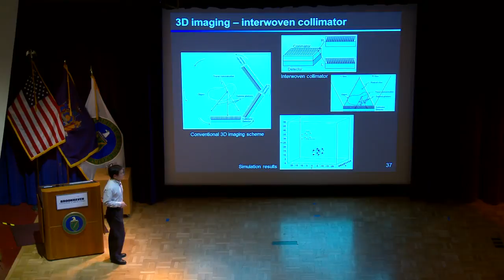But this method is not suitable for our application, because once we insert the probe in the rectum, we have no option to rotate the probe around the prostate. So we came up with an idea. Suppose this is the original collimator with all the parallel holes facing up. We separate them into two groups. The R group covers rows 1, 3, 5. The L group covers rows 2, 4, 6. The R group will be tilted to the right side with an angle, and then we tilt the other group in the opposite direction. In this case, in one shot, we take two views of the organ, and the shaded area here is the 3D field of view. We can feed the data from these two views into our algorithm, and then we can do the 3D reconstruction.